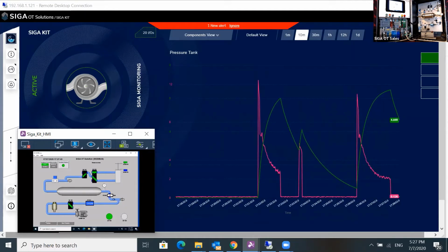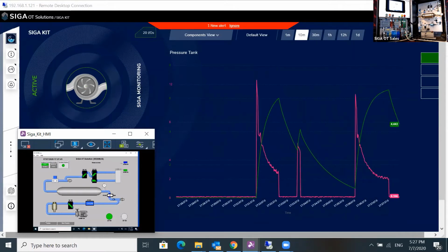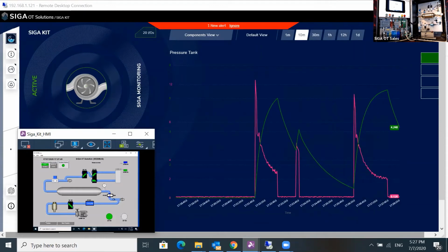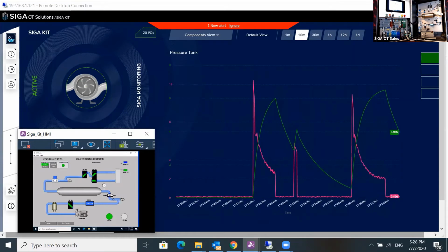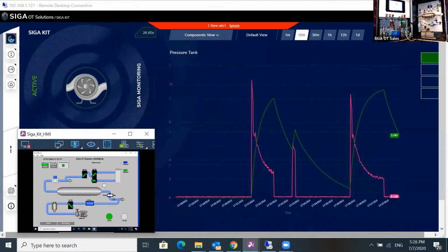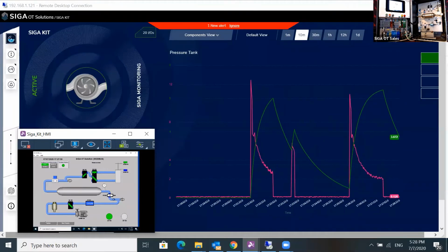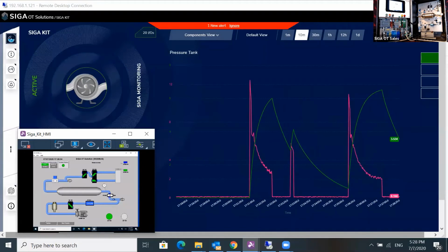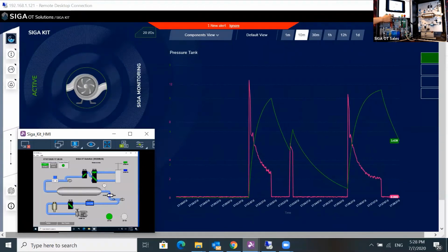The set point we will be changing inside the PLC is the piston frequency. Under normal circumstances, the set point in the piston is fixed at 2 seconds. We will change that set point to 1 second only. In this case, the machine learning engine learned autonomously and automatically the normal process and behavior, and it detects an abnormal behavior in which the piston is moving twice as fast, an event that creates a hazardous situation for a real process.